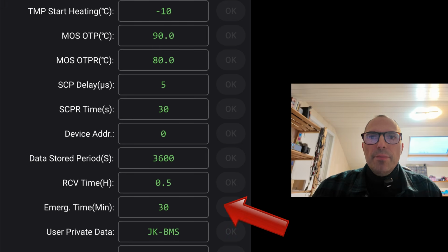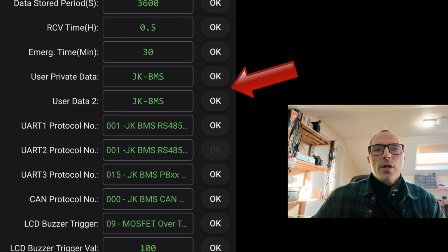Emergency time is the time the emergency setting remains active. I demonstrated this earlier in the video. You can overrule safety settings, but it's not recommended and should be avoided. After this time, the battery will be disconnected again. User private data is a free-to-use field for battery manufacturers. You can enter whatever you want. Some vendors use it to store the manufacturing date or serial number of the battery.